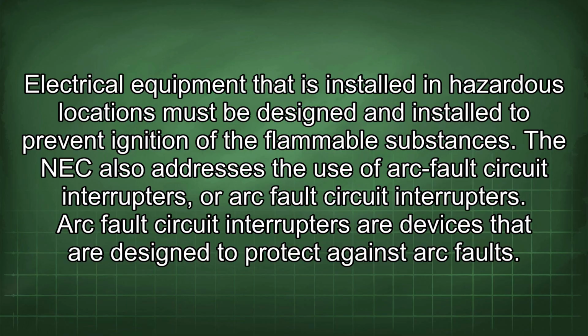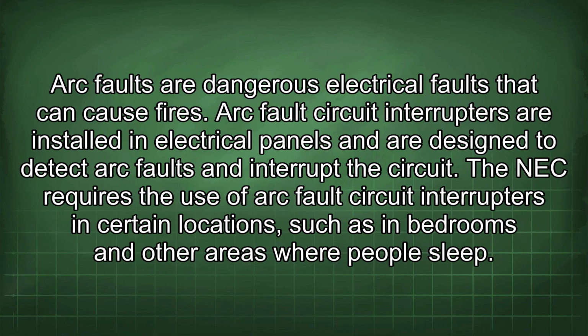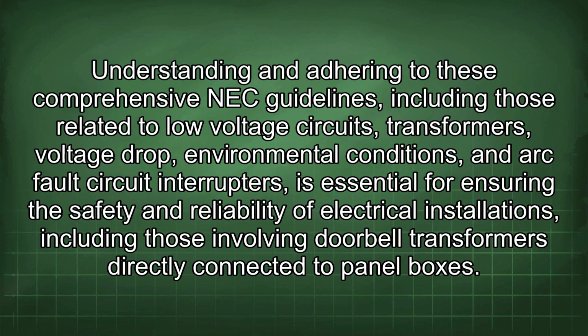The NEC also addresses the use of arc fault circuit interrupters. Arc fault circuit interrupters are devices that are designed to protect against arc faults. Arc faults are dangerous electrical faults that can cause fires. Arc fault circuit interrupters are installed in electrical panels and are designed to detect arc faults and interrupt the circuit. The NEC requires the use of arc fault circuit interrupters in certain locations, such as in bedrooms and other areas where people sleep.